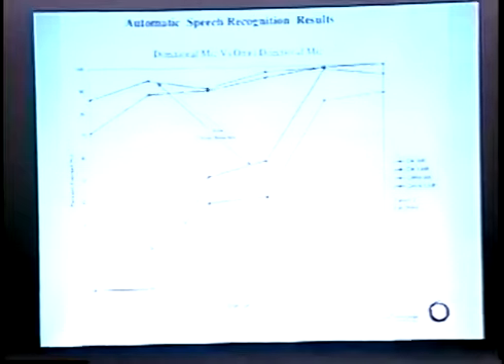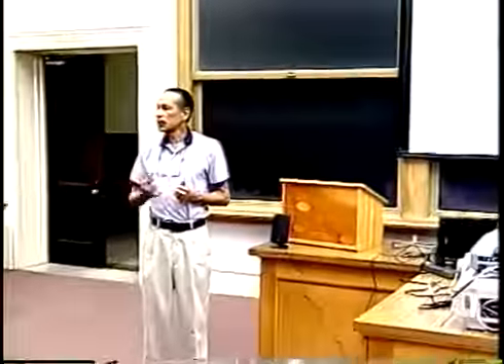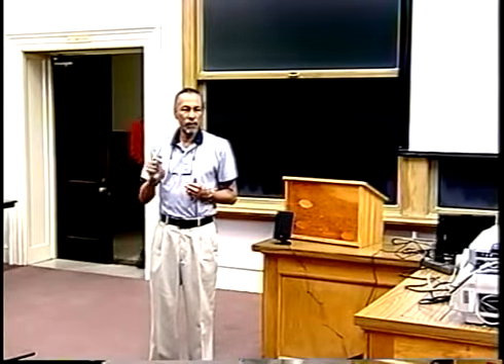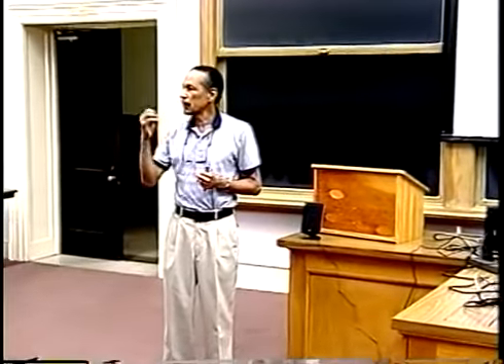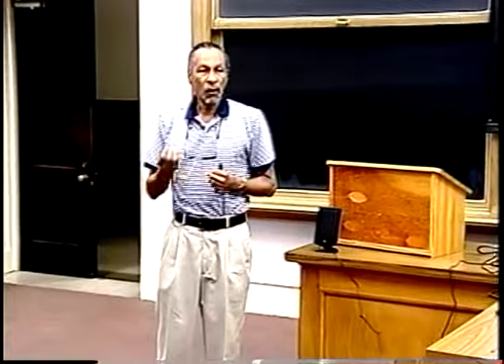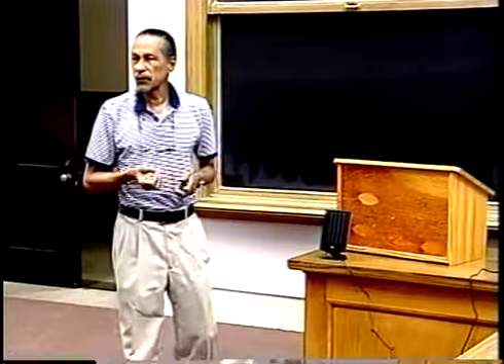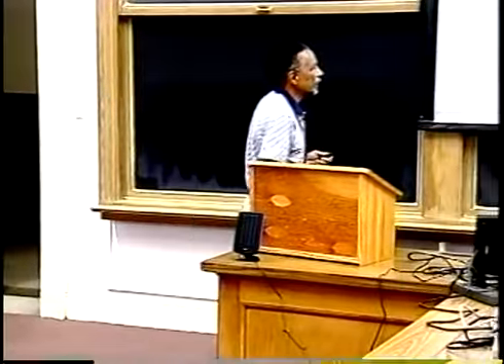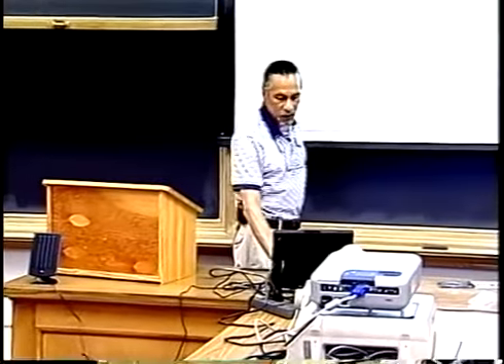One of the other things we did was to try some noise reduction schemes on top of the directional microphone. There are two things that happen here. You notice there's a limit of 12 dB of noise suppression. What happens with noise suppression or any of those schemes is that they introduce their own distortion. That distortion can be in the form of a sort of singing, a musical tone put onto the voice, or other distortions which automatic speech recognition engines just do not like. So that's all well and good.